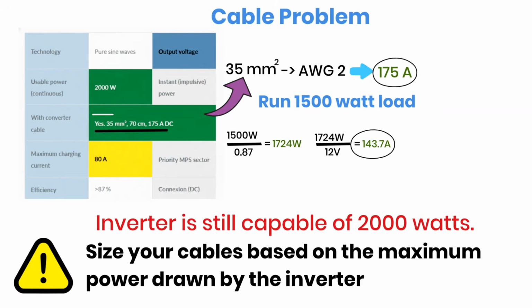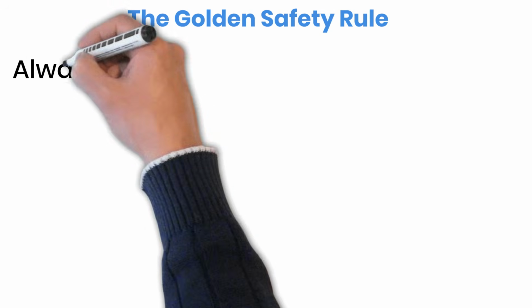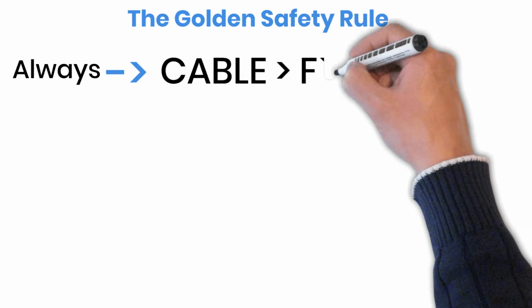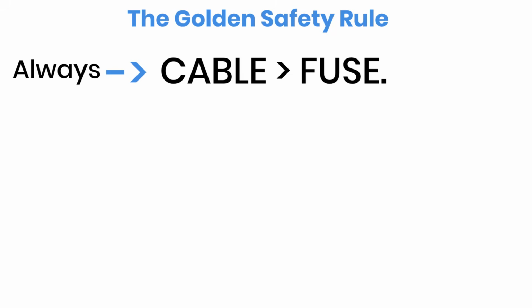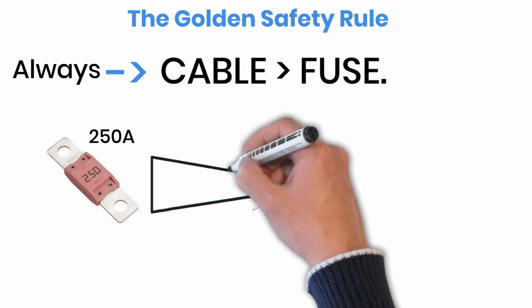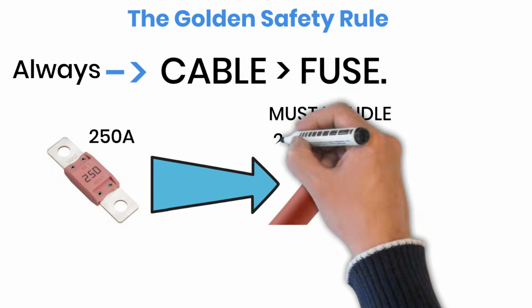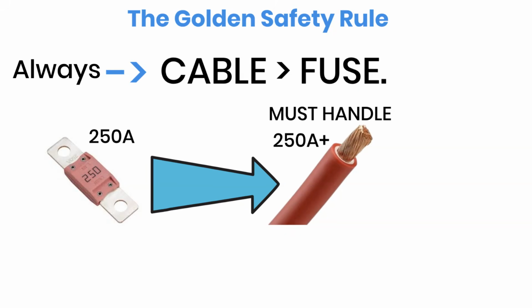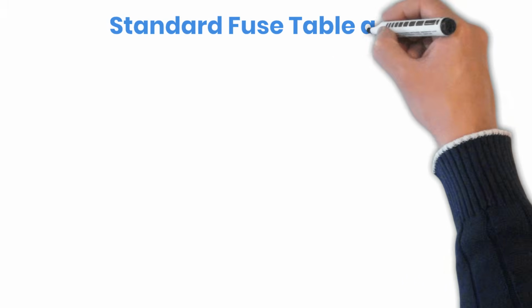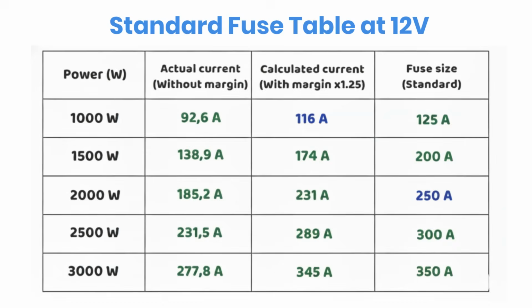Here is the golden safety rule. Your cable must always handle more current than your fuse rating. Not equal, more. So, if you're using a 250 amp fuse, your cables should safely handle over 250 amps. That usually means going thicker, like 50 square millimeter cable or similar. To make it easier, here's a simple table showing how much current the battery supplies based on inverter power, assuming about 90% efficiency. It also includes a 20% safety margin and the closest standard fuse size.